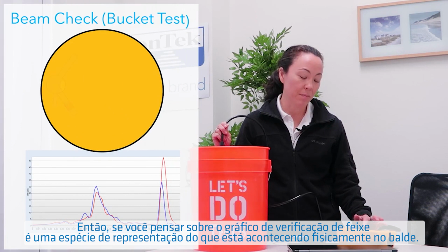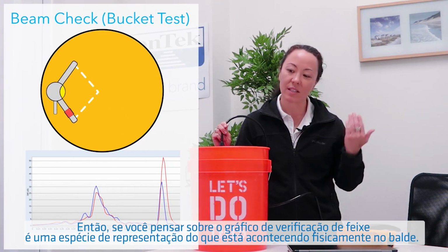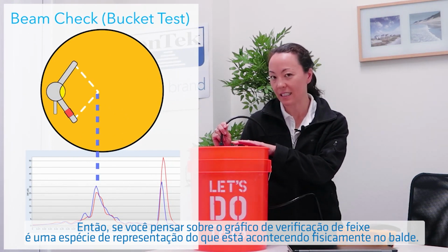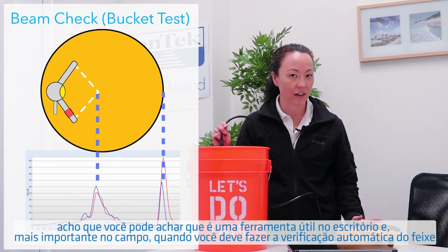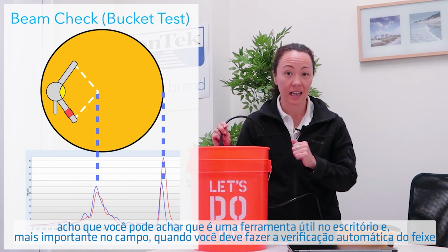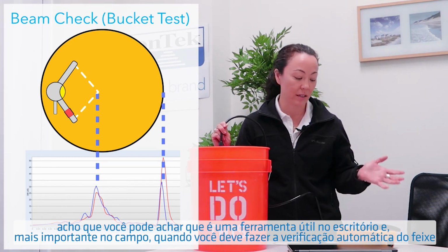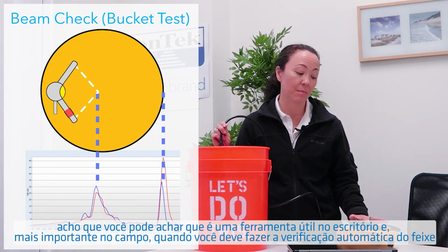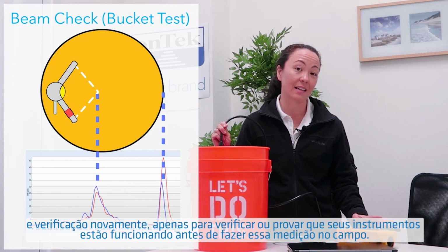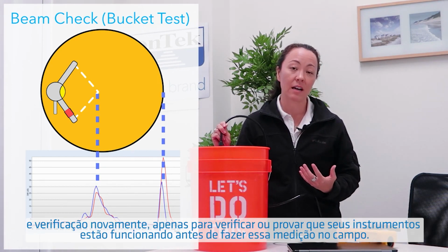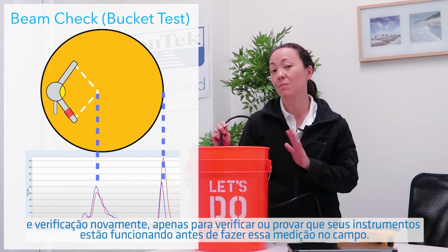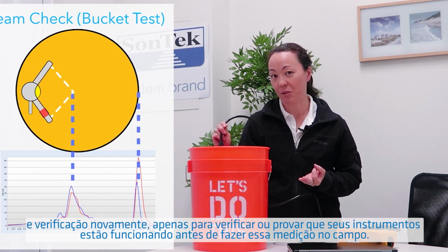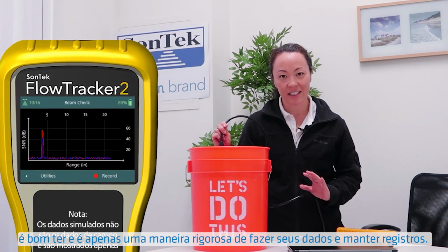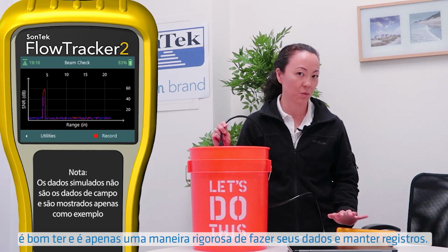So if you think about the beam check graph as sort of a representation of what's happening physically in the bucket, I think you'll find it's a useful tool in the office, and more importantly in the field, when you should do this automated beam check and beam check again, just to verify or prove that your instrument's working before you take that measurement in the field. It's just nice to have, and it's just a rigorous way of doing your data and record keeping.